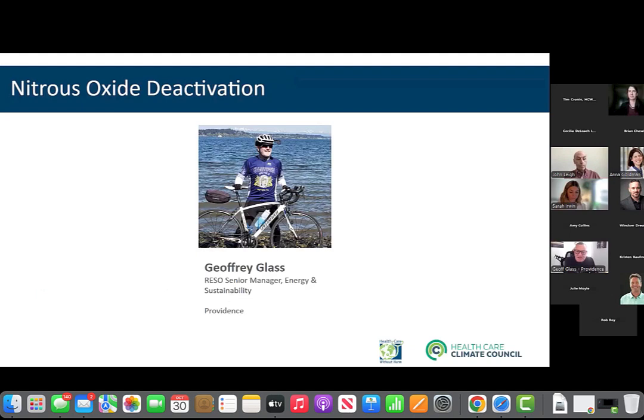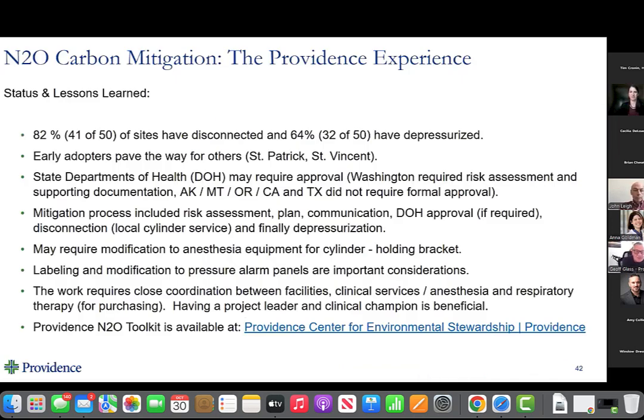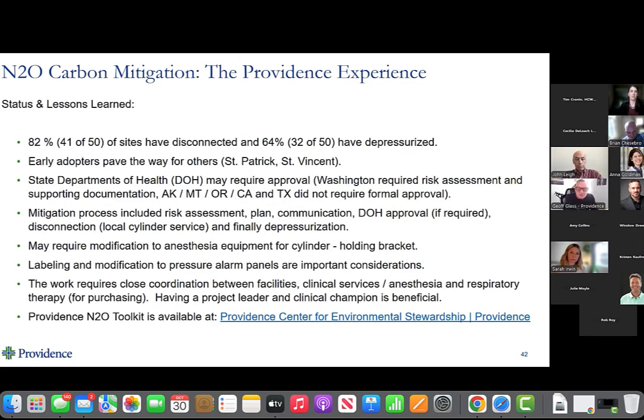I feel a little intimidated to follow you both, but I'm glad to provide a little bit more of the context and the story that is Providence's experience with deactivation. Let's go to the next slide to start that. I'm going to start with our experience and some of our lessons learned. As you can see, this is where we are right now. 82% of our sites are disconnected. You heard Brian talk about this transition; our approach includes 2 phases. One where we go through a phase of disconnecting the pipe system, but still keeping it pressurized.